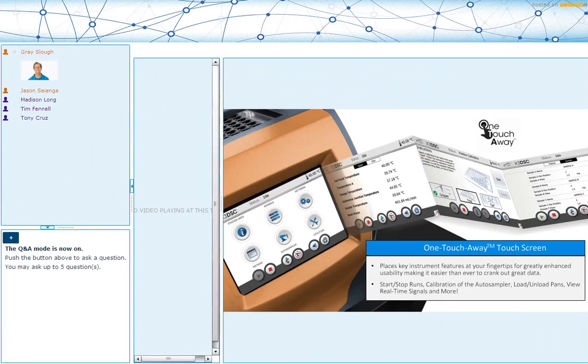So talking about the one touch away touchscreen here. The touchscreen has a lot of functionality on the instrument. As you can see here, we've done a little accordion style display showing there's a number of functions available at your fingertips. You can control the autosampler from this touchscreen. You can check the method that's running. And most importantly, you can do the calibration of the instrument.